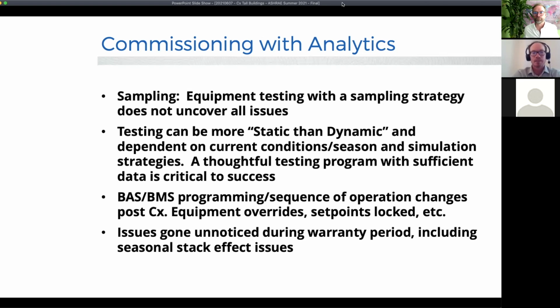And if we look at the monitoring-based side of this, analytics is certainly part of that. If there's an energy management system or something else looking at this in the background, I'm definitely an advocate for that. The other interesting point I'd like to make, and this might be a little controversial because it might upset some contractors, is that there are a lot of issues that go unnoticed during the warranty period—a lot—and we're talking about some of the tuning that needs to happen during that first year or beyond for occupancy.